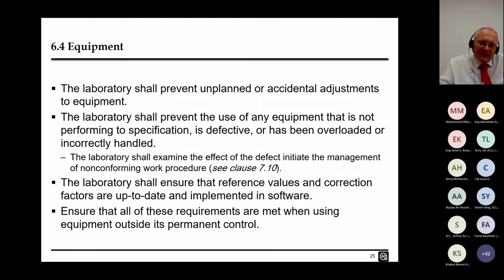And that's what we do, certainly for our reference standards, to establish if any changes have happened during transport or calibration. So definitely the requirement is that you check it working properly when it comes back. Does that answer your question? Yes, okay, thank you.